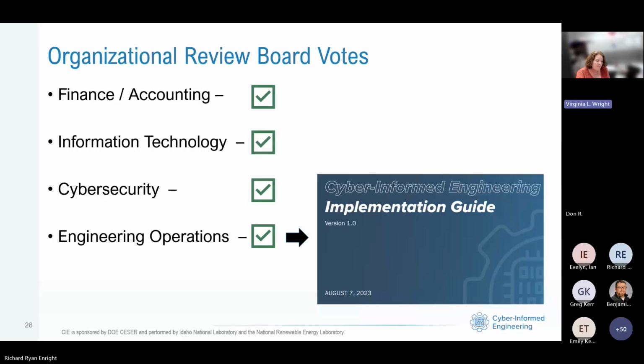With this design, the team went back to the organizational review board and reported that with the time delay relay option, it would add $20 plus a necessary outage for each water booster pump station to the cost of implementing the cloud solution. Finance and accounting was still fine with that, and engineering and operations felt comfortable that they had a solution such that even if an adversary broke through the cybersecurity, there was still something to protect the water systems.